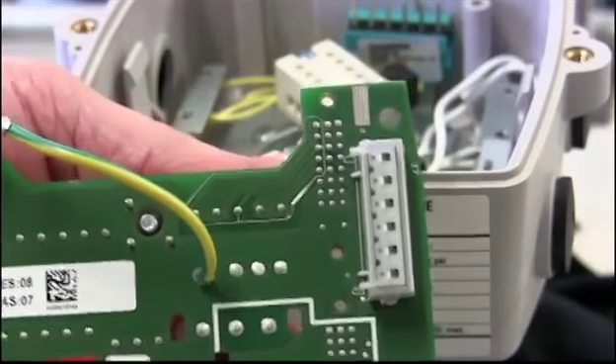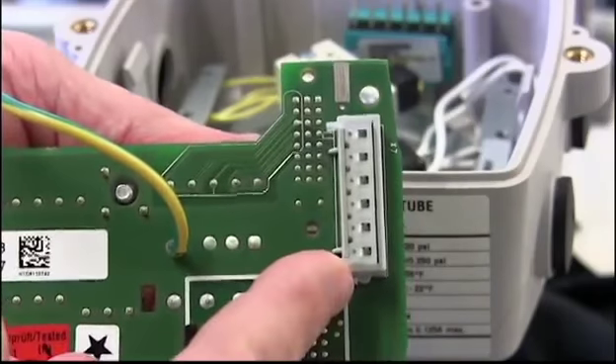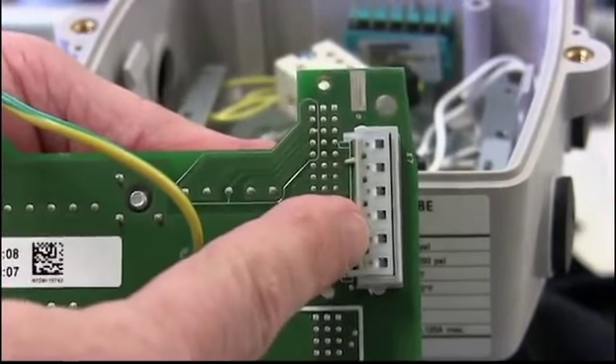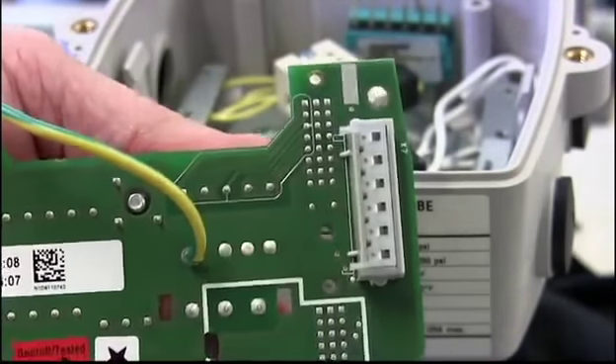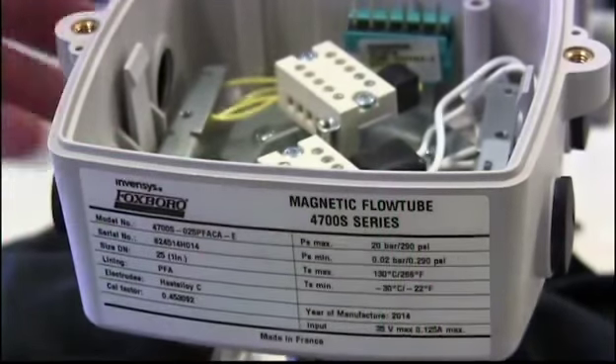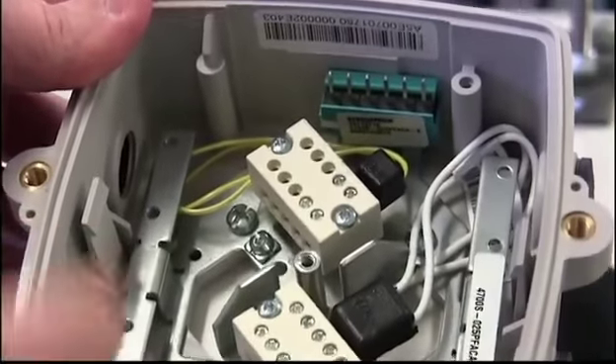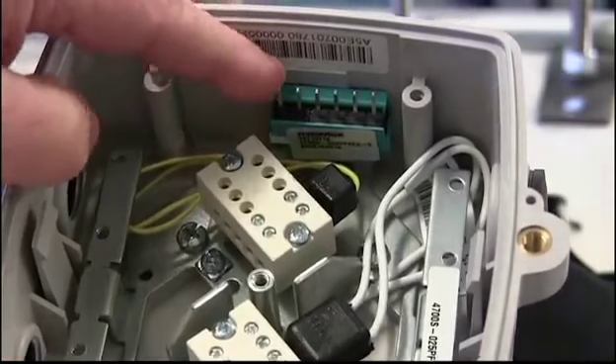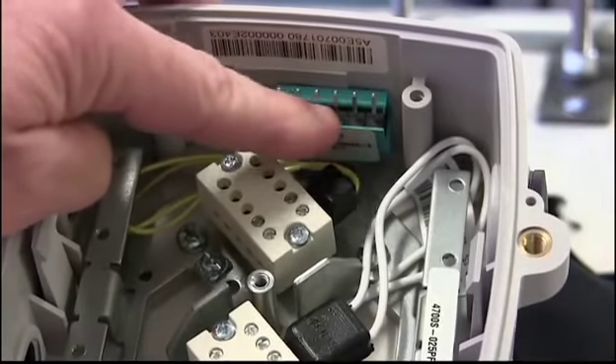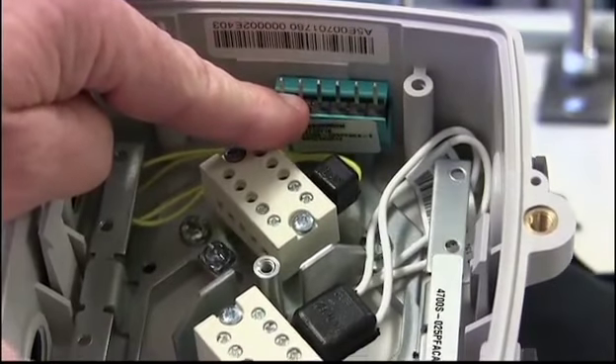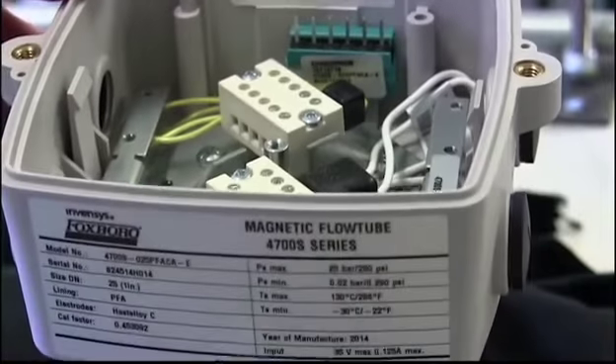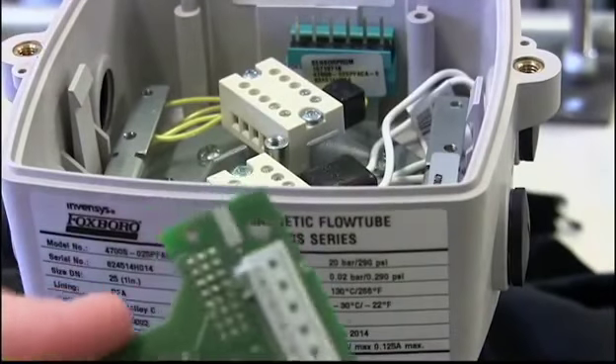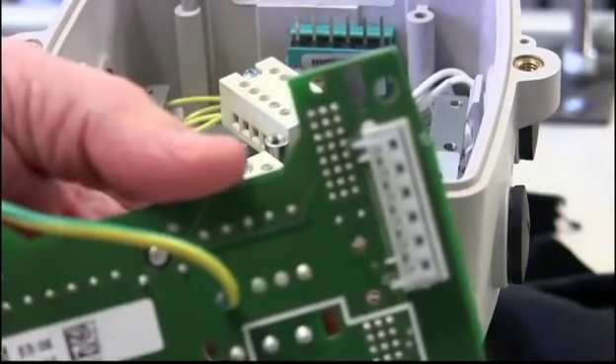You notice on the back there is a large terminal that is used for the sensor prom. If you're looking in at the flow tube here, you notice the sensor prom in the back over here that has some pretty sturdy pins. Those pins will be inserted into the slot on the back of the connector board.